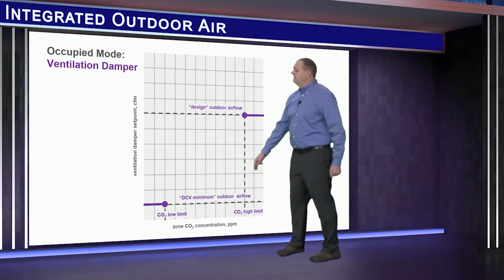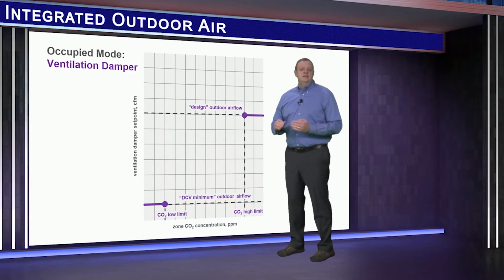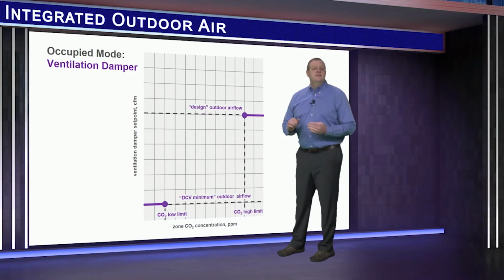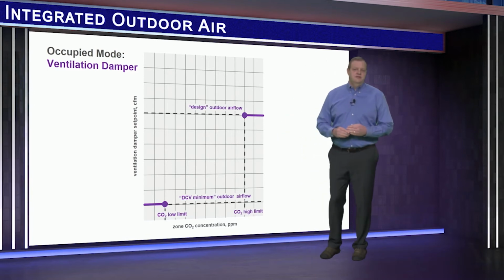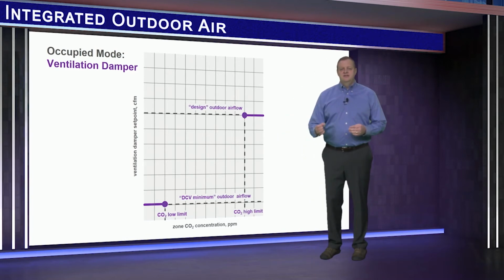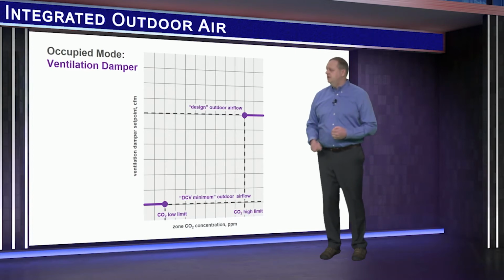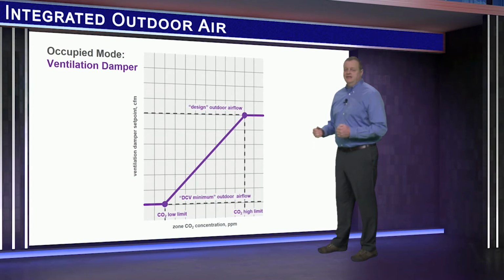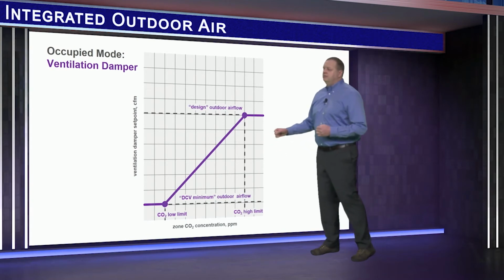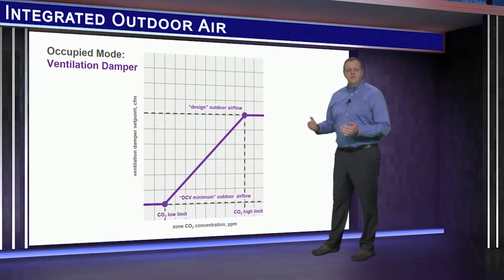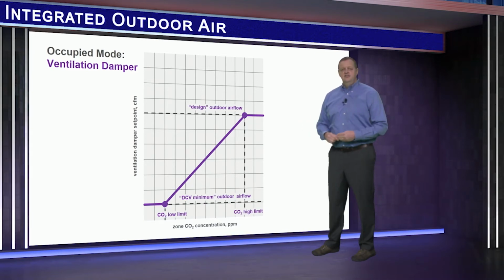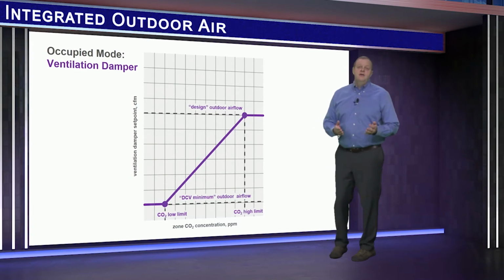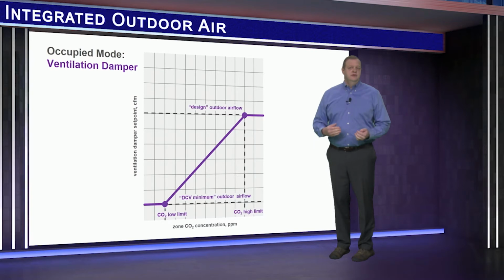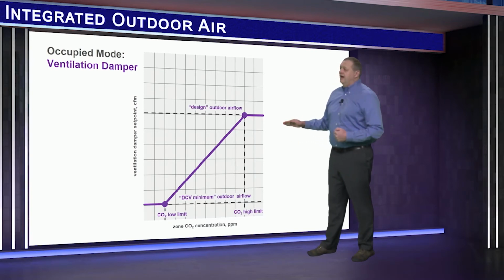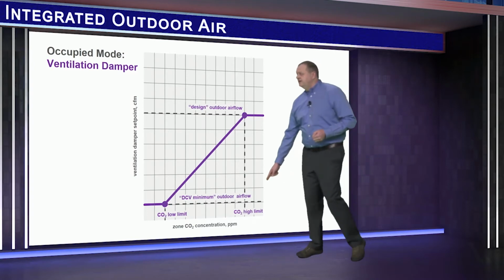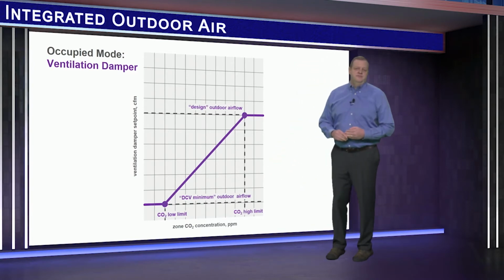When the concentration is at the low limit, this damper is controlled to bring in the DCV minimum outdoor airflow. This is the amount of outdoor air required when no occupants are currently present. It's typically the CFM per square foot rate that's listed in ASHRAE standard 62.1. And then when the concentration is between the low and high limits, the damper modulates proportionally between these two airflow set points. Note that this is the same sequence that's described in the standard 62.1 user's manual. Now, if an occupancy sensor is used instead of CO2, the damper brings in either the design outdoor airflow when the zone's occupied, or this DCV minimum airflow when no people are present.